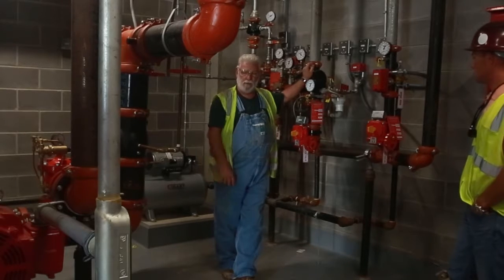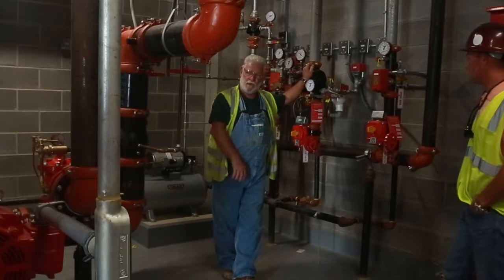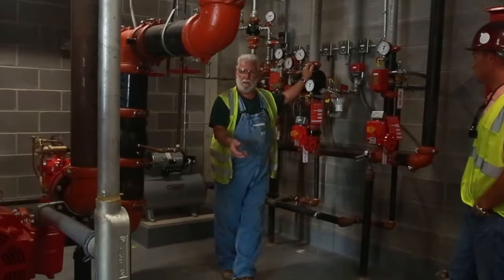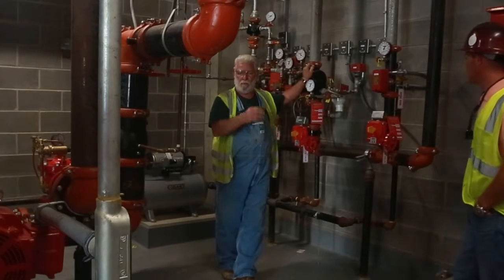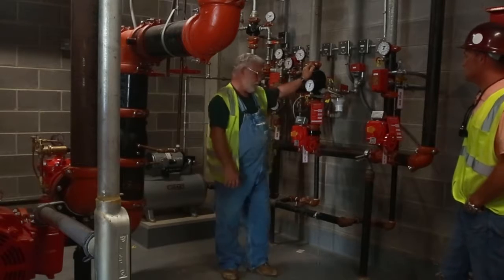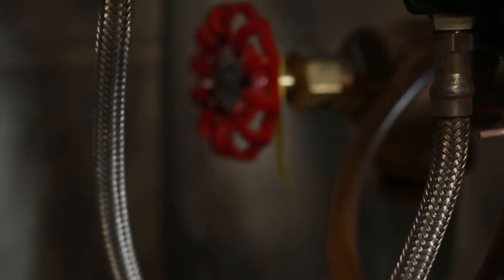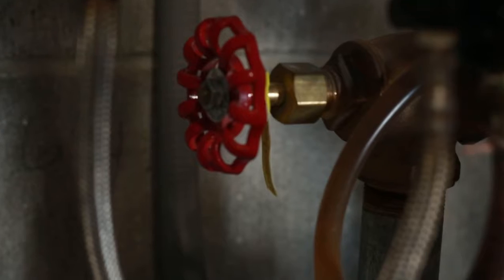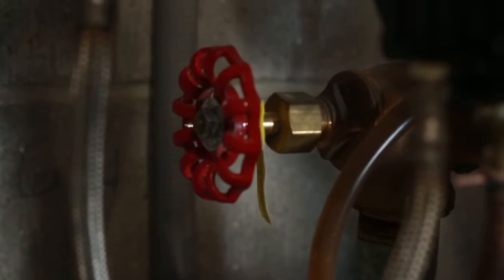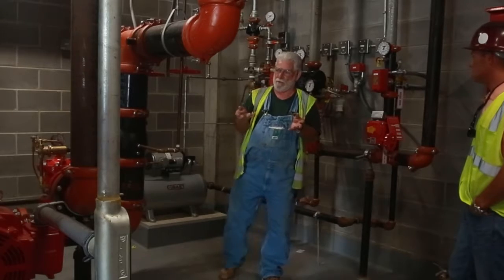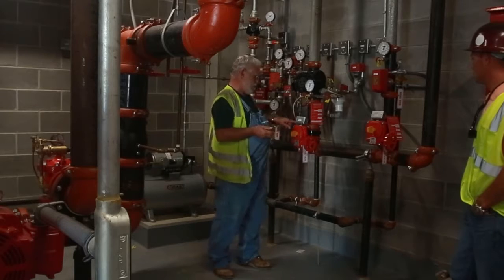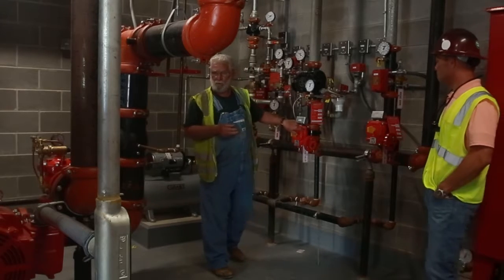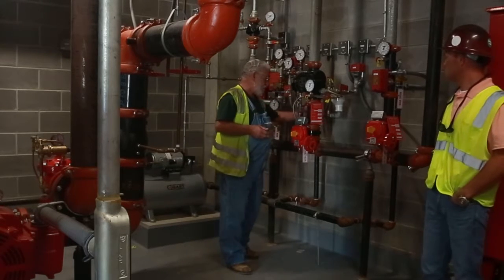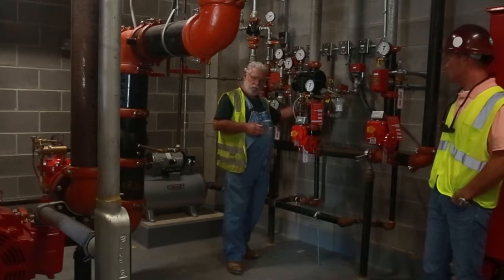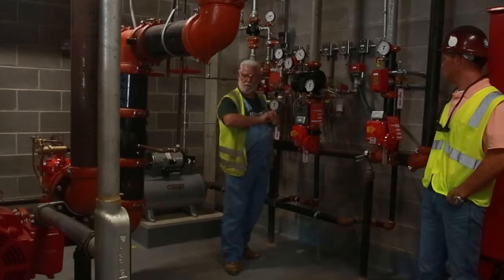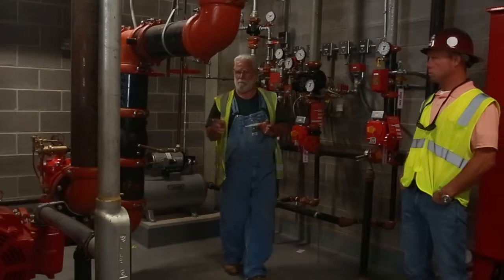And basically the same thing: when you have a fire, drain it down, replace the head or heads, and set it back up. When I say set it up, you got a knob back here that you compress, turn clockwise, and you'll hear the clapper go click. That means it's set up. And all you have to do is open the valve, start rolling water with this valve open, and then gradually close this valve, and it'll set itself up.